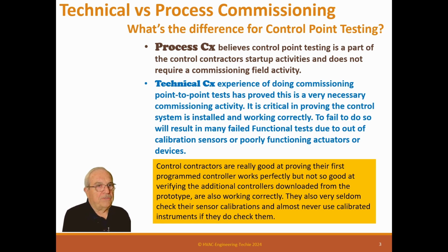Now, control contractors, I can talk about control contractors because I was one for many, many years. Control contractors are really good at proving their first programmed controller works perfectly, but not so good at verifying the additional controllers that are downloaded from the prototype are also working correctly. They also very seldom check their sensor calibrations and almost never use calibrated instruments if they do check them. So the calibration, I guarantee you, will be a problem, and you'll need to check that.